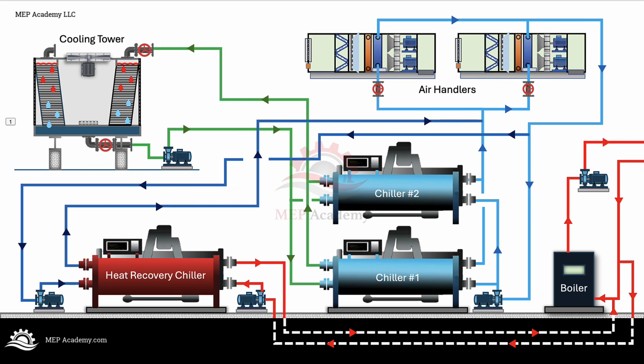This is why heat recovery chillers are commonly considered for hospitals, campuses, laboratories, hotels, high-rise buildings, central plants, and facilities with year-round interior cooling loads. These buildings often have simultaneous cooling and heating needs. They are removing heat from one part of the building while adding heat to another part of the building. A heat recovery chiller connects those two needs. Instead of throwing heat away outdoors, the system asks a better question. Can we use that heat somewhere else?